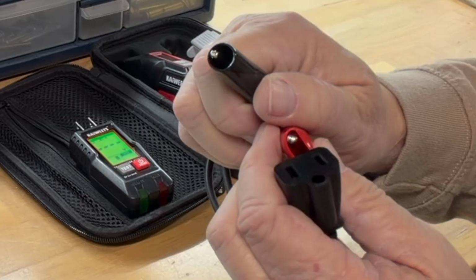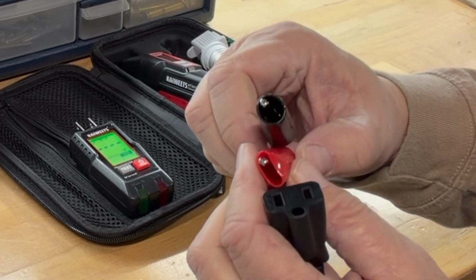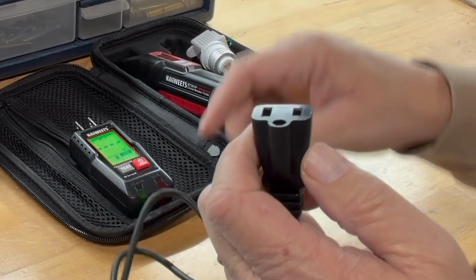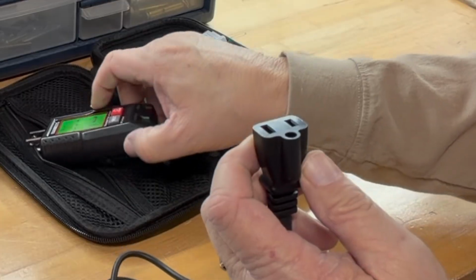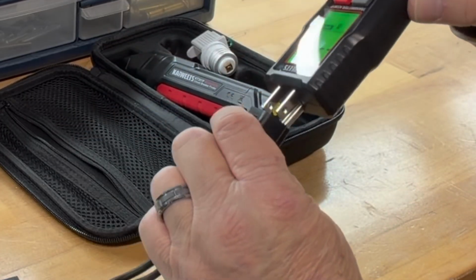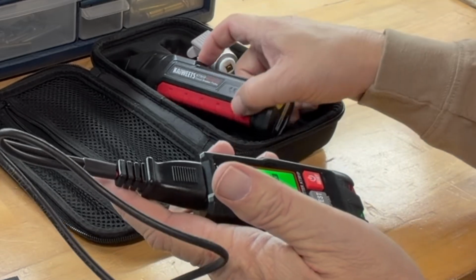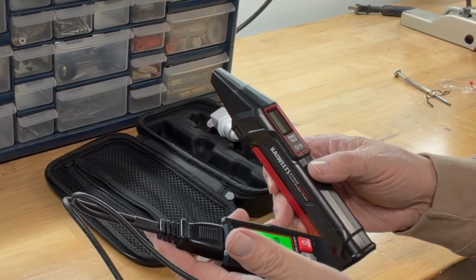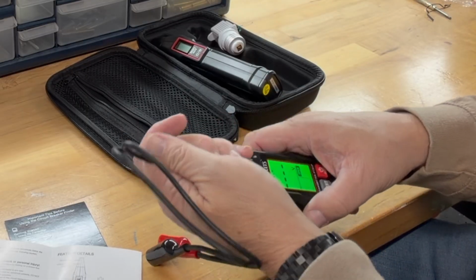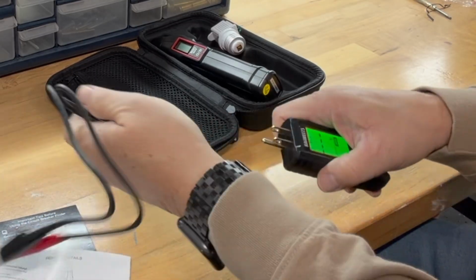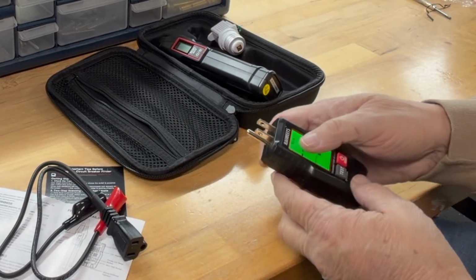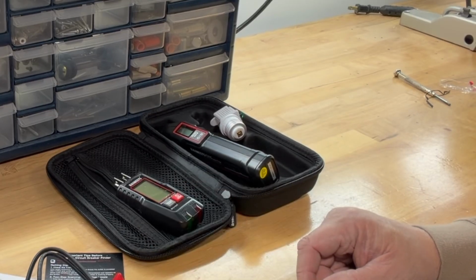You would just clip those onto the bare electrical wires, and then you would take your tester, plug it into here, and then you could go to your circuit breaker to scan and test your circuit there. So multiple ways that you can check for circuits depending on the conditions. So let's go ahead and perform a couple of tests.